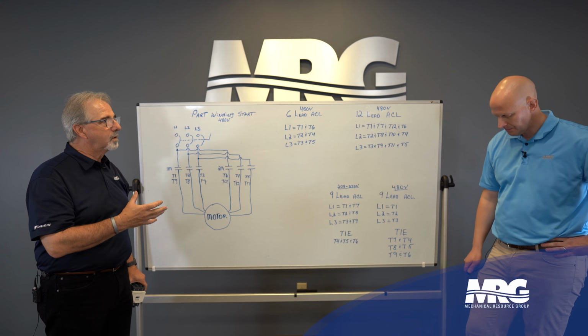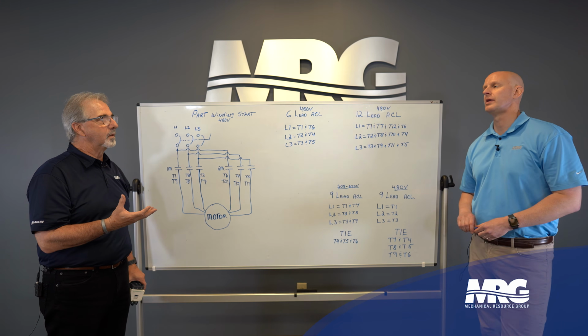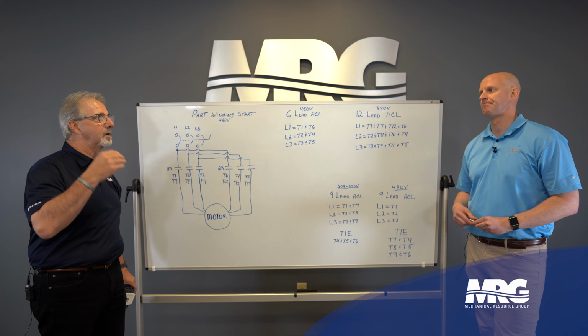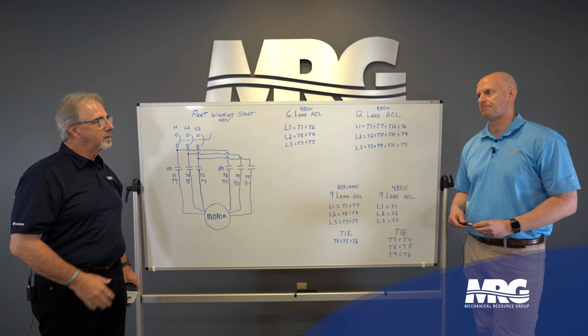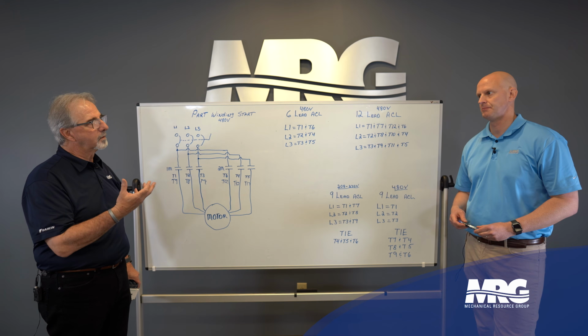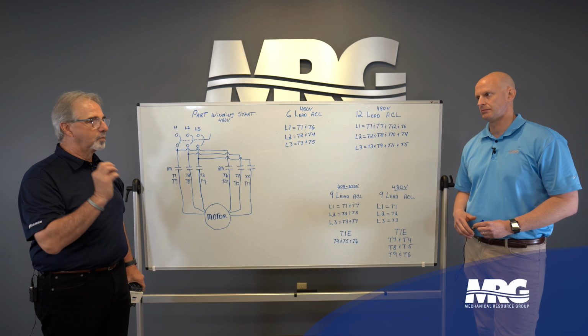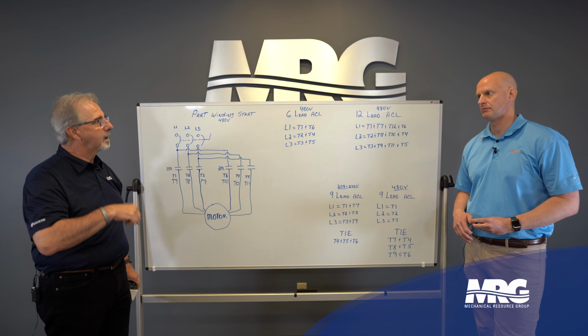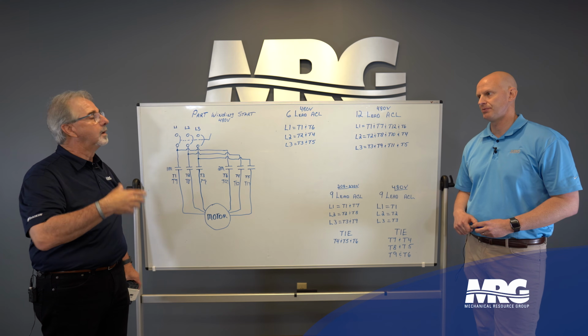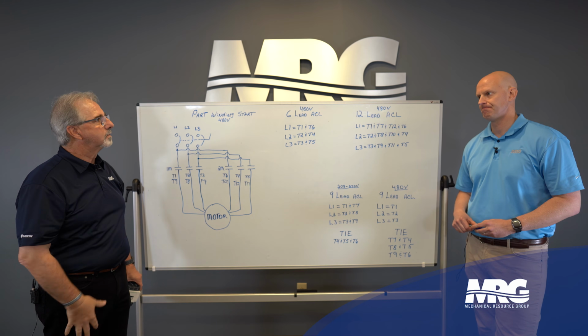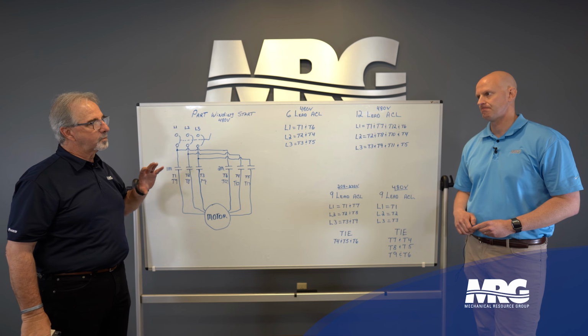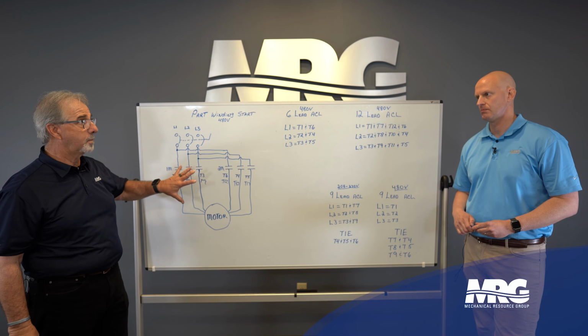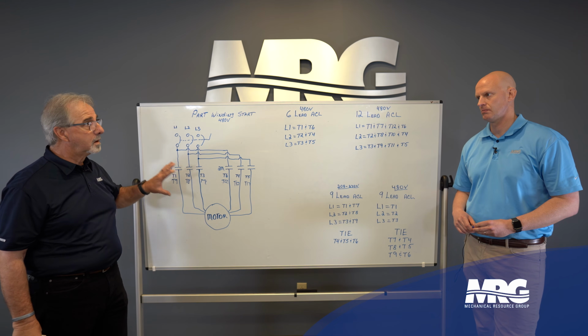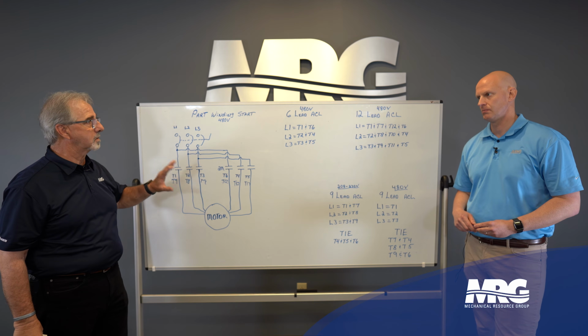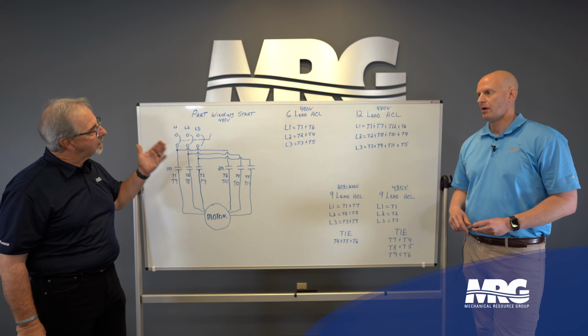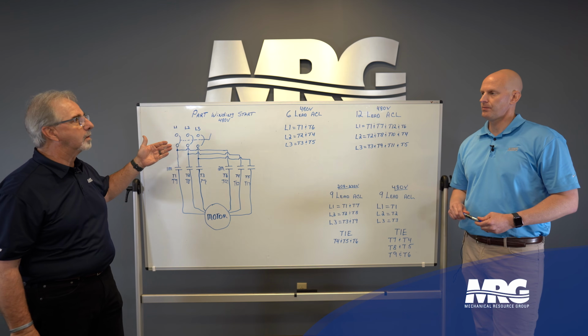Now, on small motors, John, we've gotten away with it. Yeah. Okay, but when you start hitting that 5, 7.5, 10 horsepower, you really start looking at that. And so acceptable methods are going to be like Polaris lugs, ring terminals with a machine screw through it and a nut and then rubber tape and 33, or split bolts. So those are the kinds of things, and especially when we're connecting this up, absolutely, positively never use wire nuts. Always use an acceptable connection method. Yeah. So that kind of covers our 9 lead and our part winding start.